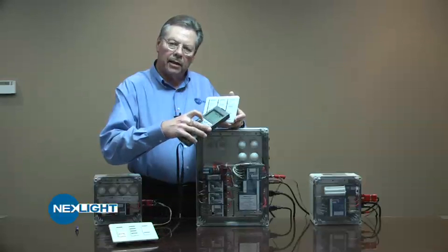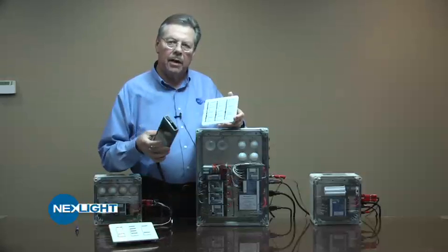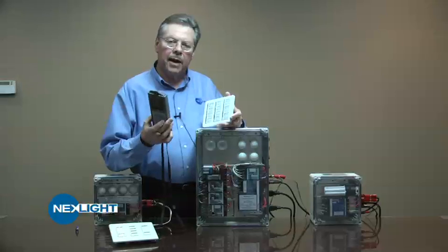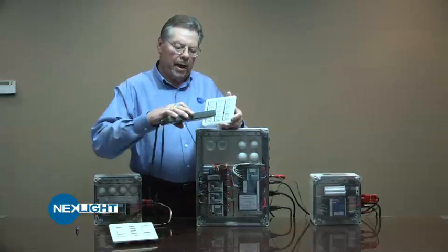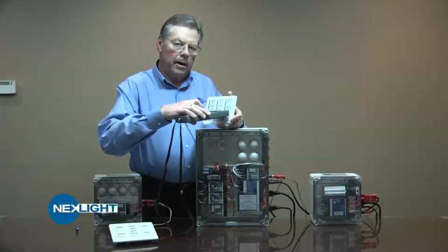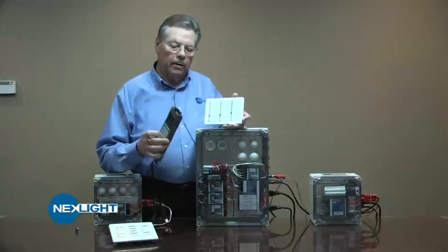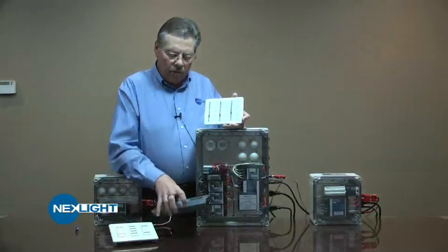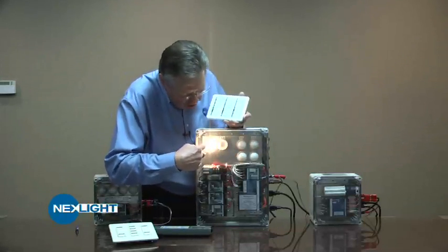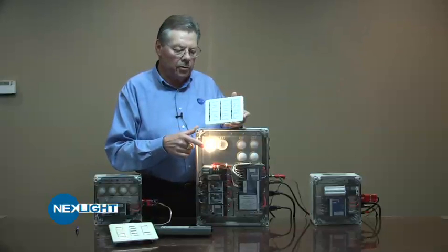You'll hear that you actually get a little beep, a little chirp. That chirp is telling you that it cannot read the bus signal. It's not actually getting a connection with the system through the IR access point. So we have to reposition our controller, our programmer, and when it works properly, you'll see that you actually get the full tone. And it's going to tell us right now, of course, that we are actually programmed right now as 2-1, which happens to be this address that we've used for this particular dimming application.